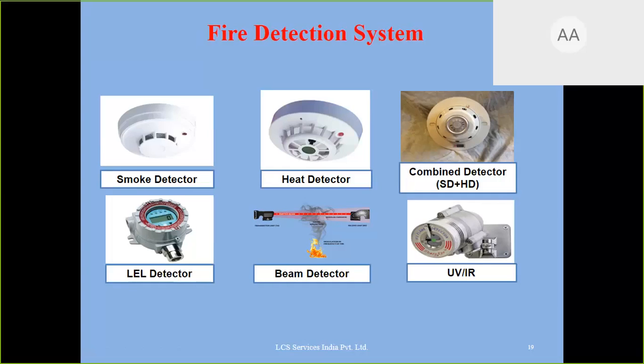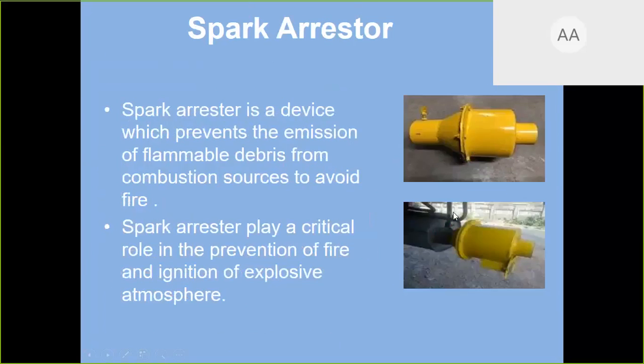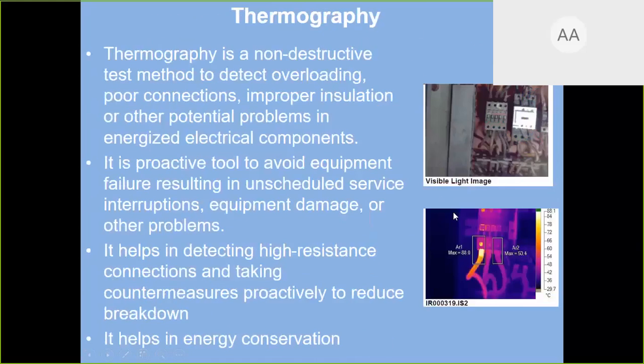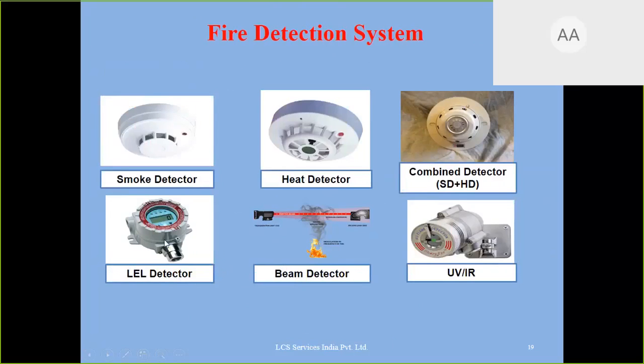Similarly, PNG, pipeline natural gas. Now, most companies have pipeline natural gas by which they are running their DG set, paint shop, oven, incinerator, and many other things. This LEL detector can be used for any gas, whichever is flammable, whether it is LPG, PNG, or any other gas. If you install it, it will proactively give you an alarm and signal that there is a leakage. You just have to close the valve, so that the leakage is detected, the countermeasure is taken, and then you start the operation. So this is a must for any gas leakage.